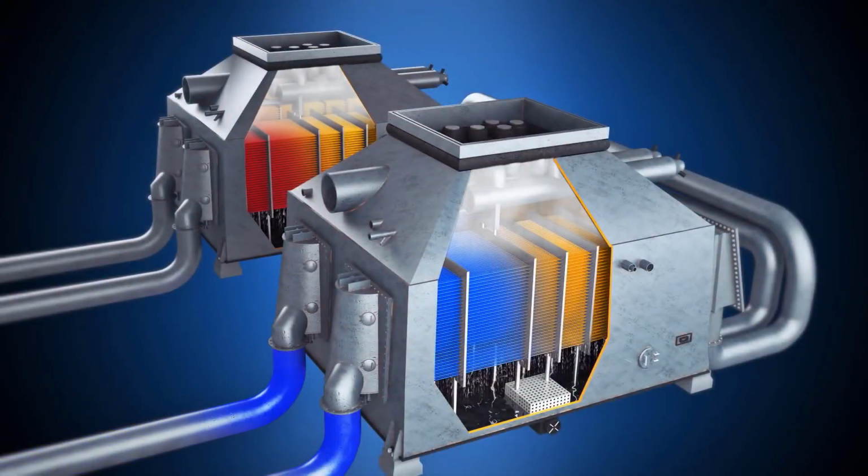Plant Miller uses a closed-loop circulating water system that allows water to be reused over and over. One way we use water is in the condenser, where steam enters from the turbine and condenses back into water as it passes over tubes filled with cool circulating water, which is chlorinated river water from nearby Mulberry Fork of the Warrior River. The condensed water moves into the hot well where it re-enters the system to be reheated, turned back into steam, and continue its use throughout the plant.